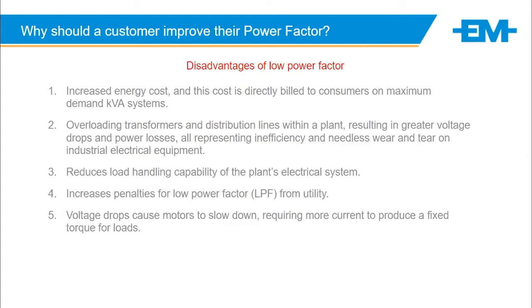Obviously it reduces the load handling of the plant because you're overloading the transformers. With the inefficiency, you would have increased penalties for low power factor from the utility. And as things start up, as that demand kicks in, if your PF is bad, you would have voltage drops, causing motors to slow down, requiring more current to get the torque to get that load going.